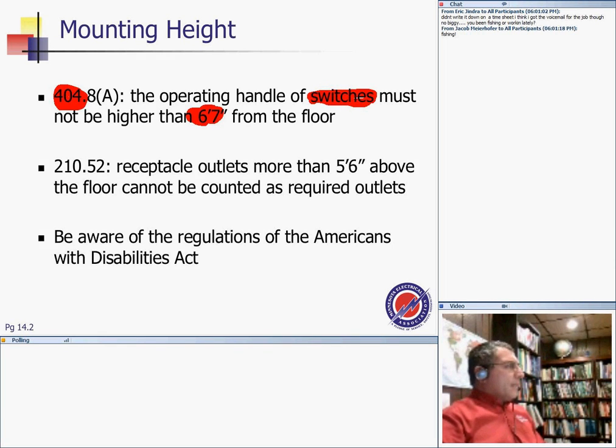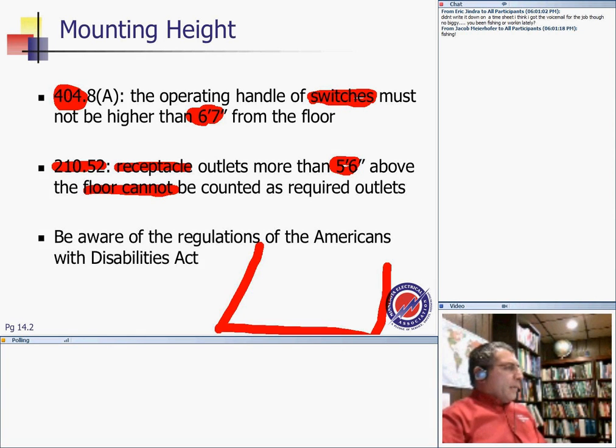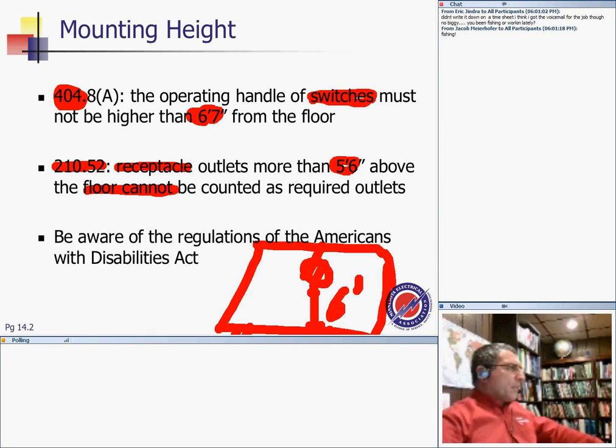Another thing that you guys need to understand, also receptacle outlets. With outlets, if you put a receptacle higher than 5.5 feet, then the receptacle would not count as one of the receptacles required in the code. For example, if I decided to put my receptacle right in here, and from here down to the floor was 6 feet, and I need receptacles on the floor, right? By code, in residential habitable space, you need them every 12 feet in between, right? And 6 feet from edges. Now, the receptacle at 6 foot high would not count. So beware of these height limitations of receptacles. I call it the height limitation of receptacles.